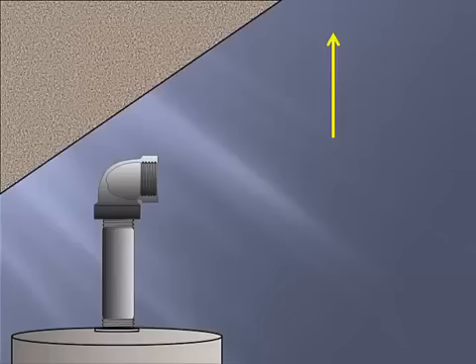What we'd like to work on for today's lesson is how to take a center to center measurement, subtract for the fitting allowance, to accurately cut the end to end piece required for the offset.